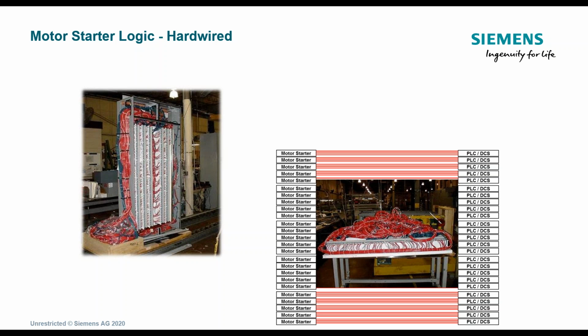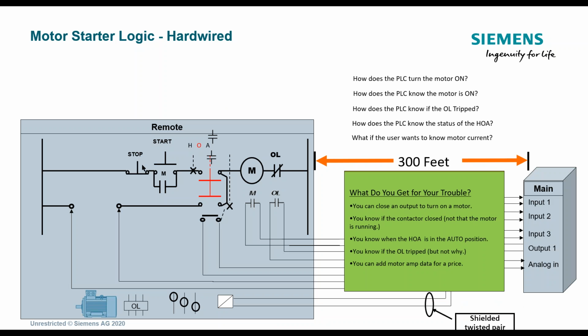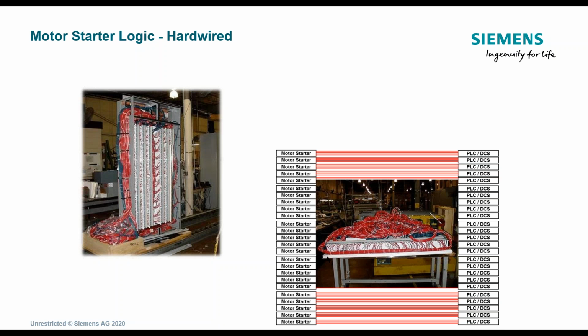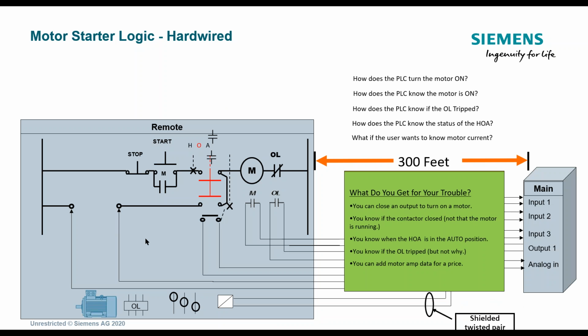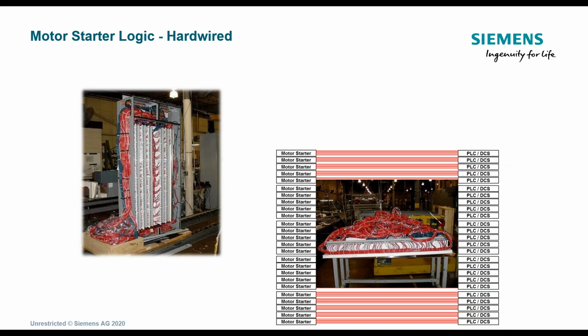But here's an actual scenario of all that wiring that we had in the previous diagram, per motor. And here's all the wiring. Each of the wires that you see in these motor control centers or control cabinets lands at the buckets, and they are all the data coming from the scheme that you see here with the inputs and outputs and so forth and so on. So with introducing field bus, we remove all this wiring, and the communication is down to one cable itself.